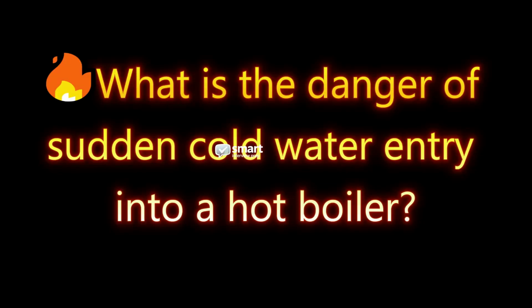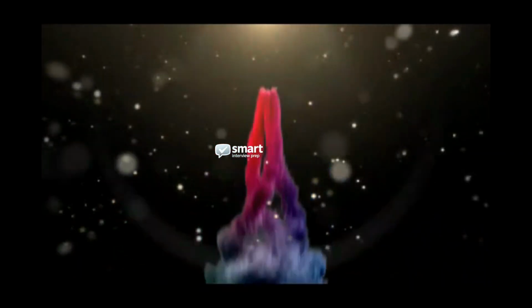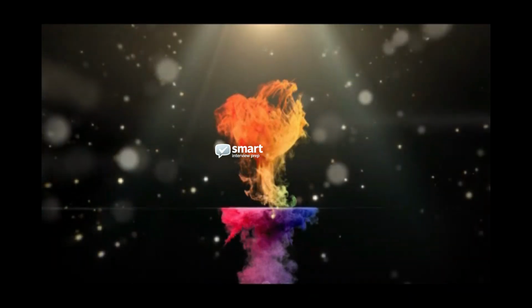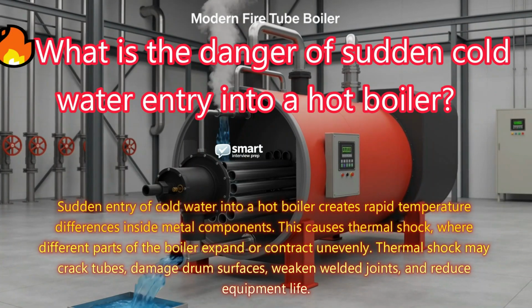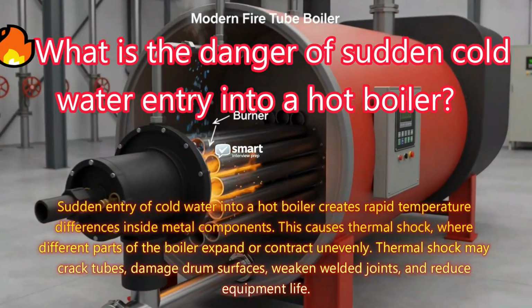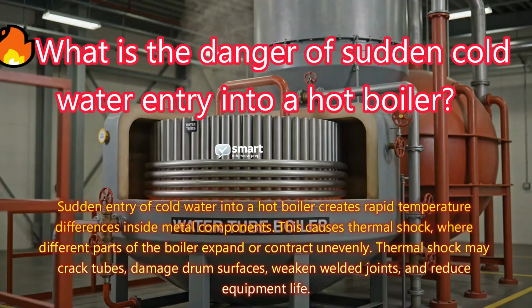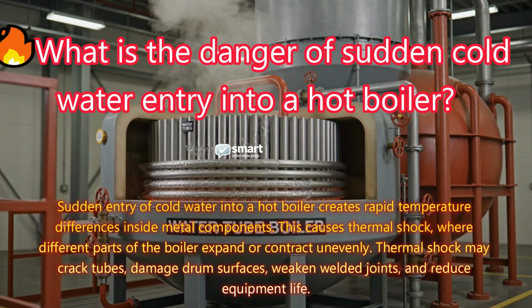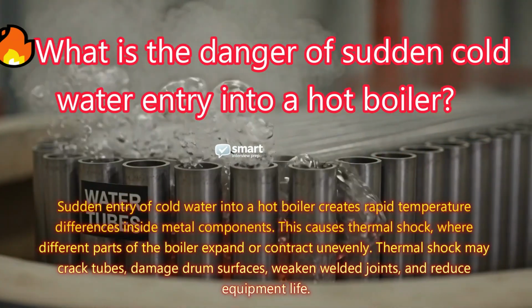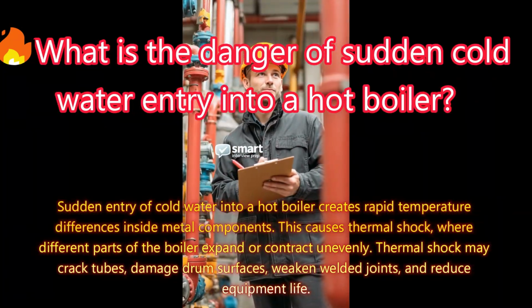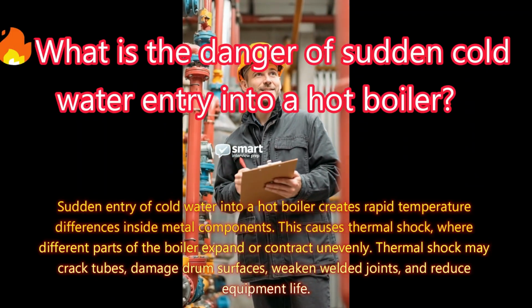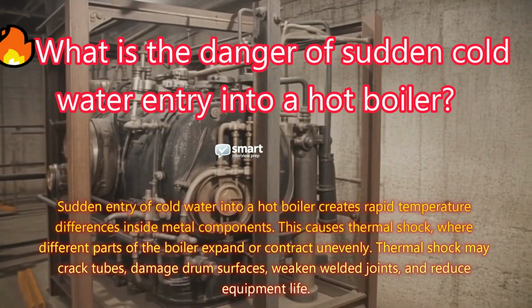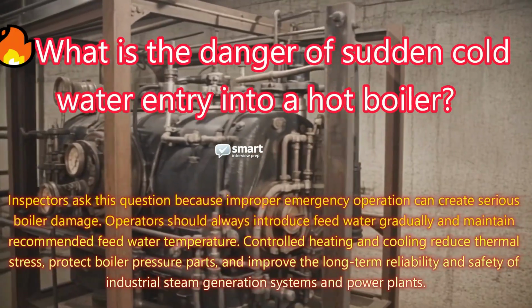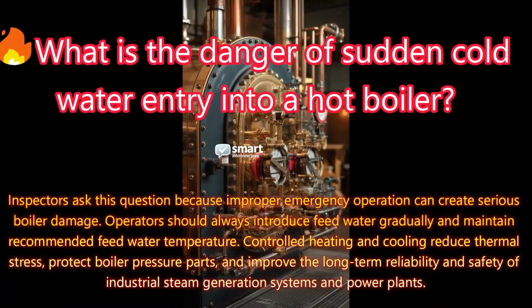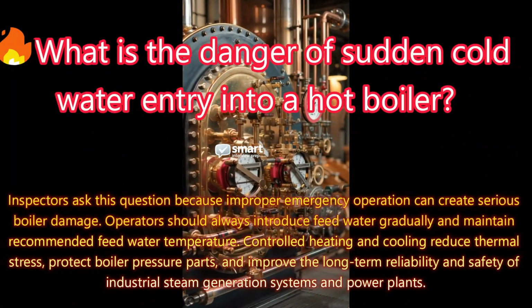What is the danger of sudden cold water entry into a hot boiler? Answer. Sudden entry of cold water into a hot boiler creates rapid temperature differences inside metal components. This causes thermal shock, where different parts of the boiler expand or contract unevenly. Thermal shock may crack tubes, damage drum surfaces, weaken welded joints, and reduce equipment life. Inspectors ask this question because improper emergency operation can create serious boiler damage.